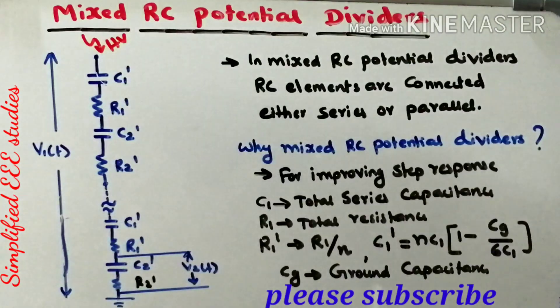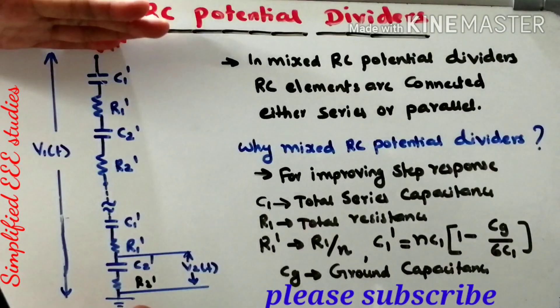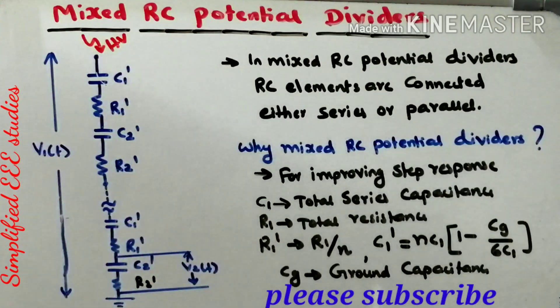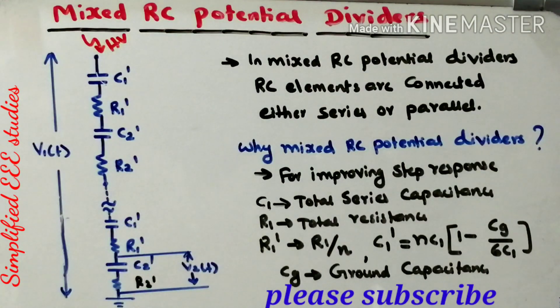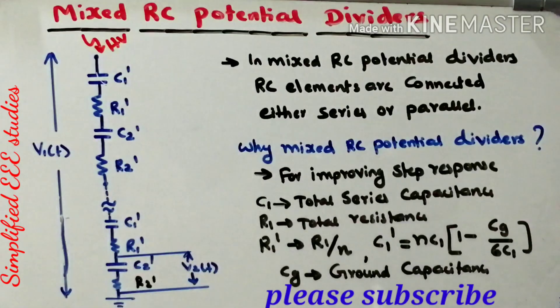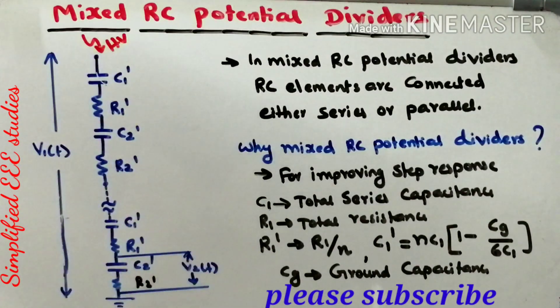You can divide the whole circuit into a low voltage arm and a high voltage arm. The output of the low voltage arm will be directly connected to measurement devices — either an electrostatic voltmeter, VTVM, or any other device — so that you can get a sample of the voltage which you applied externally.